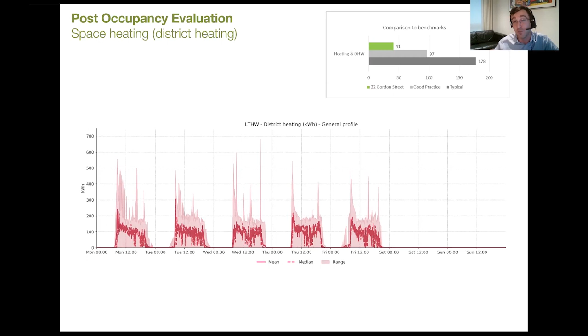But one thing we found through user surveys, and MSc researchers doing additional studies, was that the building is being used out of hours and on weekends. So there were some complaints about comfort, particularly during those periods. This warranted, through the post-occupancy study, a need to look at those controls again - are there periods of the year, say exam times, when people are in the model workshops, where the heating should be on for longer periods and still be within that CIBSE good practice benchmark.